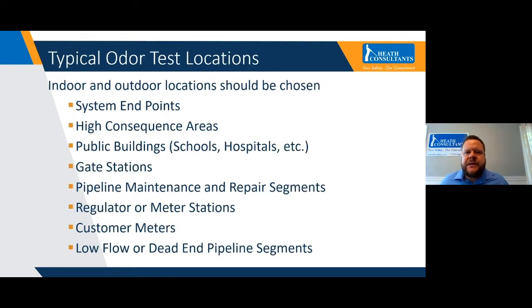So another factor that goes into how you set up your monitoring and testing program is the test locations. It's very important that you test at the endpoints of your system. So you may have adequate odorization in some of the main areas near your odorizer station. But as you get towards the end of your system, it's very possible that the odorant would dissipate or get absorbed. And at that point, you want to make sure to check at the endpoint so that the customers that are further towards the end of the system are also getting adequate odorization. Also, very important, as we mentioned before, the high consequence areas, the public buildings with large gatherings of people, whether that be schools, hospitals, high-rise buildings, churches, etc. It's also important to check at customer meters, and the reason is you might have adequate odorization in your distribution system, but you want to check the actual service line that runs to your customer to make sure that odorization is traveling with the natural gas and is actually detectable either at or beyond your customer meter.